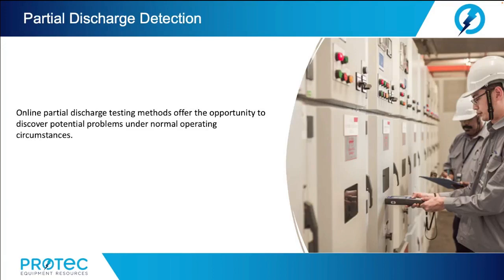Online partial discharge testing methods offer the opportunity to discover potential problems under normal operating circumstances. The online approach is a non-invasive, non-destructive, predictive test procedure. These tests can be periodic scans to obtain a quick assessment of your asset, short-term monitoring over longer time periods to provide a more accurate assessment over changing conditions, or continuous monitoring to analyze assets during day-to-day operation to detect deterioration and to raise an alarm or call to action if partial discharge activities reach a critical level.